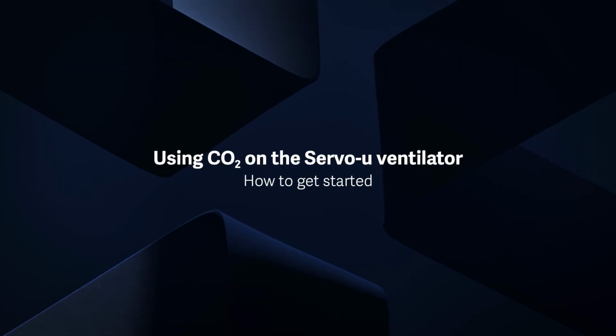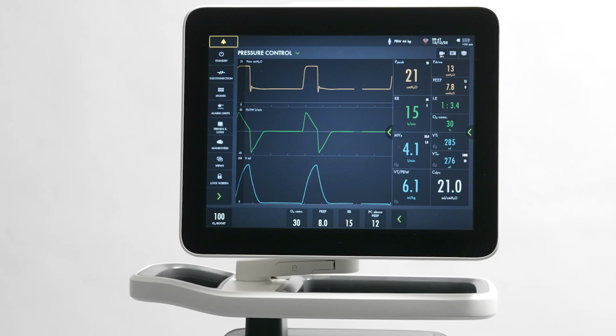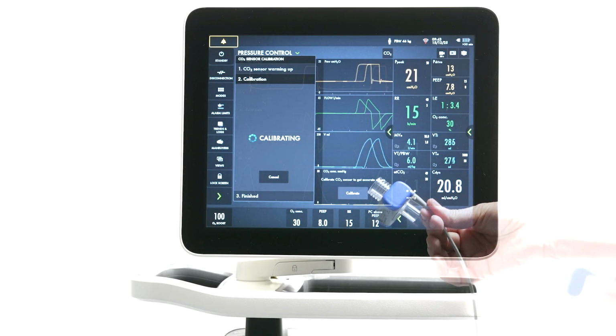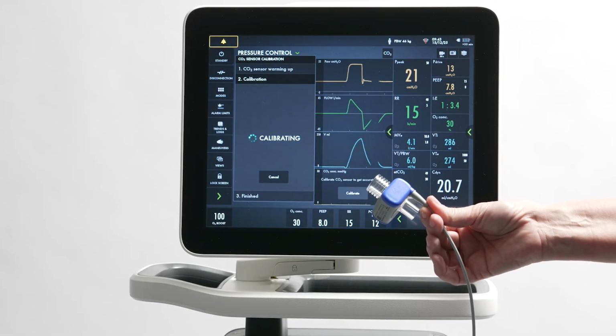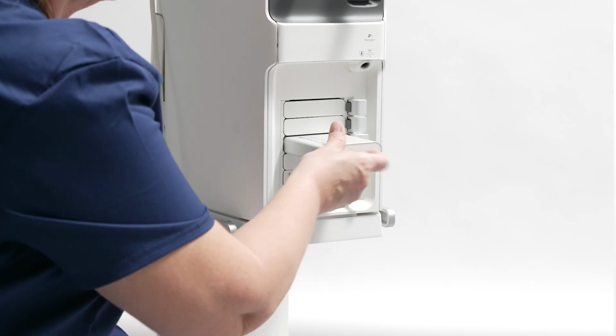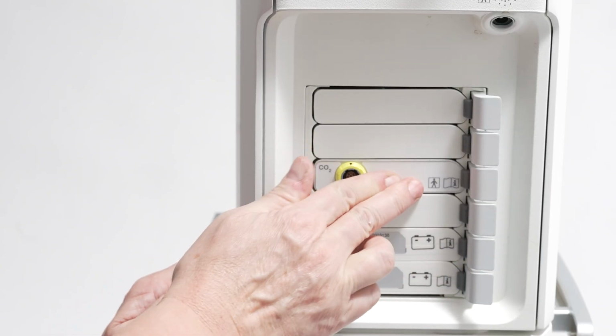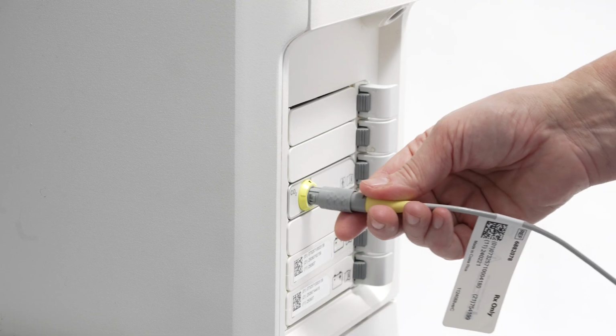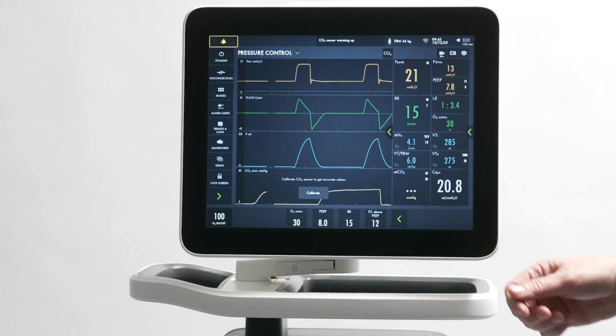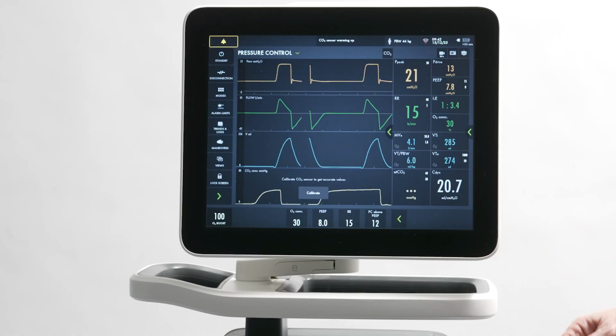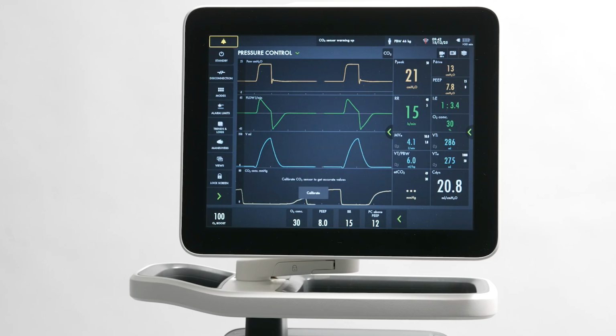Welcome to how to get started using the CO₂ with the Servo-u Ventilator. We'll walk through the CO₂ analyzer calibration process. Insert the CO₂ module and connect the CO₂ cable. When the CO₂ module is inserted, the symbol becomes visible on the screen. We will now go through how to calibrate the sensor during ventilation.